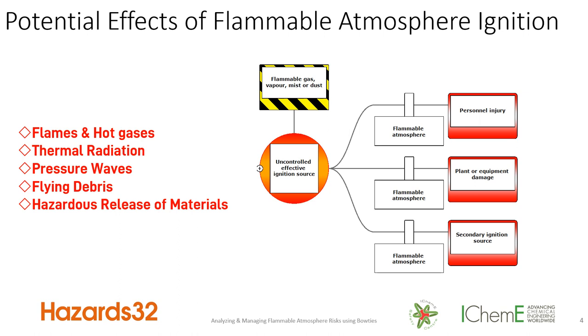There are a number of outcomes from the ignition of a flammable atmosphere. It can generate flames and hot gases, heat or thermal radiation. The explosion can generate a pressure wave that may lead to flying debris or hazardous release of materials — the combustion products may themselves be toxic. We can have effects on people, which is our key focus to protect life, but you may also experience damage to plant, equipment, or buildings, and there may be secondary effects where one ignition becomes a source for a connected piece of equipment.